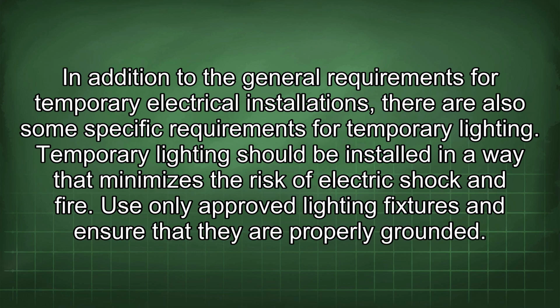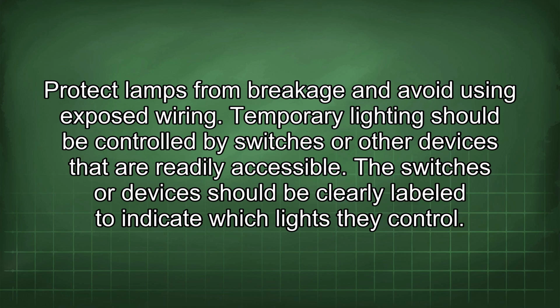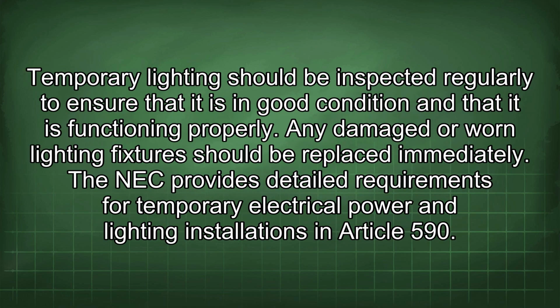In addition to the general requirements for temporary electrical installations, there are also some specific requirements for temporary lighting. Temporary lighting should be installed in a way that minimizes the risk of electric shock and fire. Use only approved lighting fixtures and ensure that they are properly grounded. Protect lamps from breakage and avoid using exposed wiring. Temporary lighting should be controlled by switches or other devices that are readily accessible. The switches or devices should be clearly labeled to indicate which lights they control. Temporary lighting should be inspected regularly to ensure that it is in good condition and that it is functioning properly. Any damaged or worn lighting fixtures should be replaced immediately.